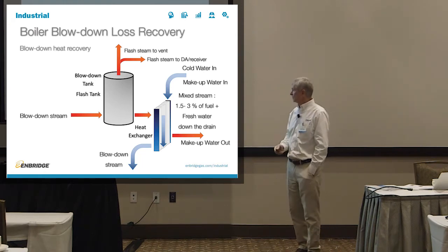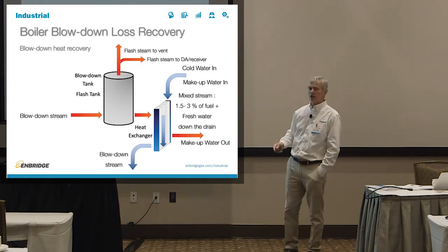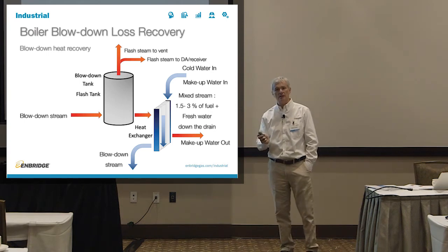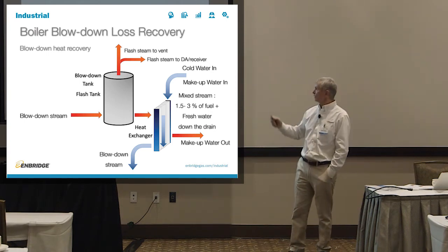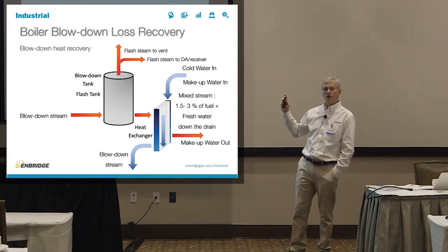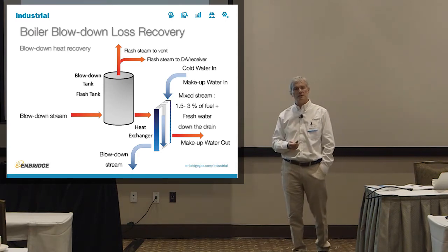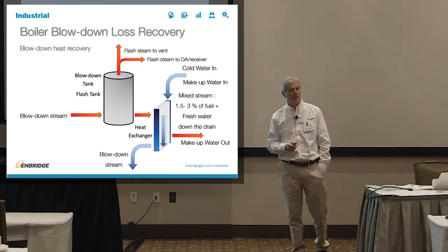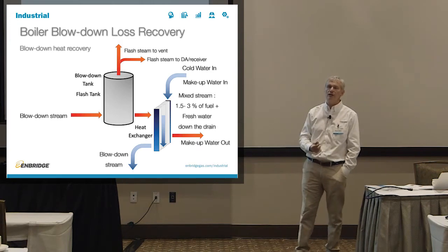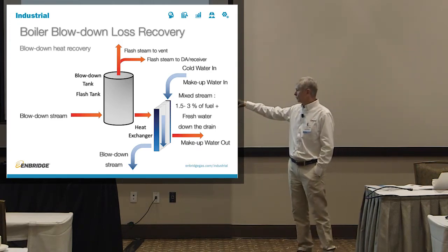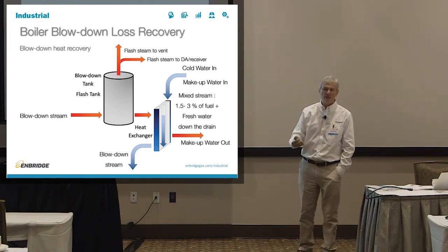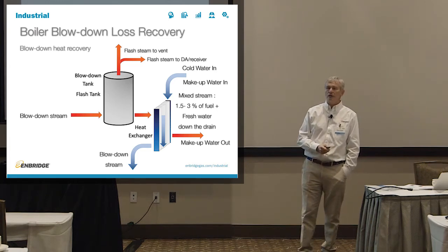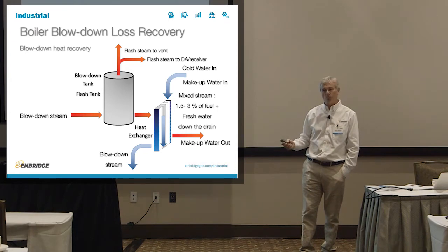The better step is, when you have that heat exchanger, you then put in a flash tank, and instead of venting the steam that comes in from the boiler, you actually recover that steam and put it back to the deaerator or to some sort of receiver for the low pressure steam. So now you've recovered all the energy that you could. Your blowdown stream is now at about 60, 70 degrees F. You don't have to mix it with the cold water. It's a win-win situation.